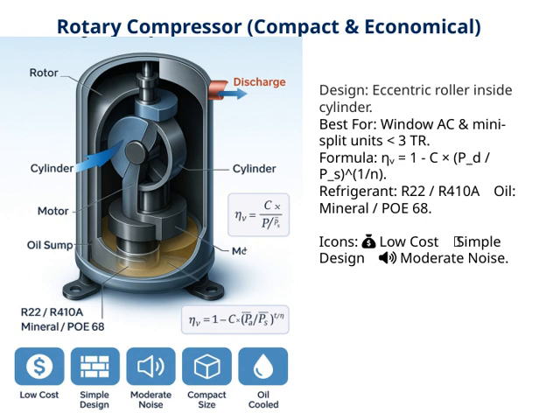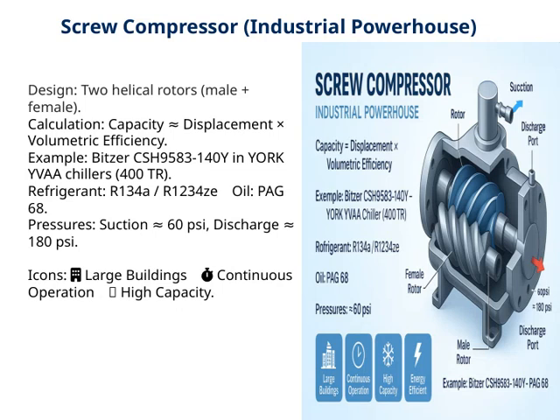Let's talk about screw compressors, which are truly the industrial powerhouses behind many large-scale cooling systems. They use 2 helical rotors, one male and one female, that work together to compress the refrigerant. This design is highly efficient and reliable for continuous operation. When calculating their capacity, we look at the displacement, essentially, how much refrigerant they can move, and multiply that by the volumetric efficiency.